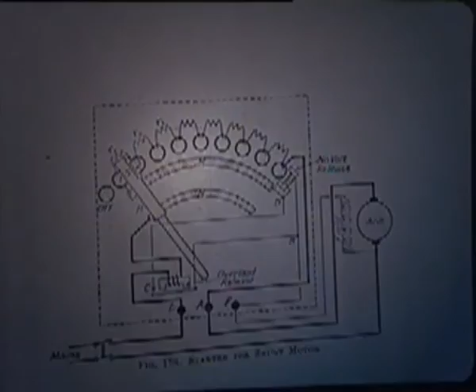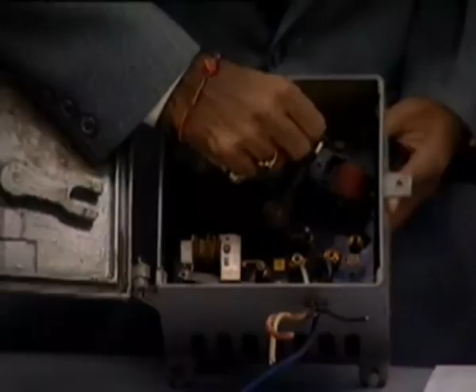Now this is the handle which can be moved to start the machine up to here, and since there is no supply, if you leave it, it goes back to that position because it is de-energized. These are the different studs, and internally there are different resistance elements. If you move it like this, slowly the resistances are disconnected, and this is the iron piece which gets attracted to this magnetic core. Now this is what we discussed as a no volt coil. While it is fully working as a motor, it will be in this position, and when the supply is removed, it goes back to the original position, because there is no voltage here.